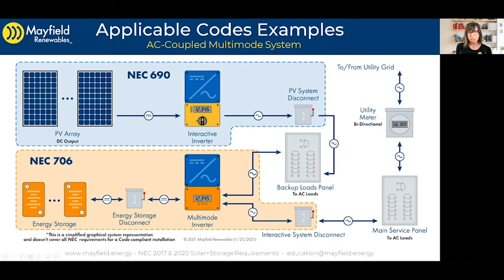The last thing to bring up is the voltage limitation. We need to keep in mind that DC circuits can't be over 600 volts DC on the DC side for a dwelling unit, unless they are not accessible during routine maintenance. We want to make sure we're considering that code requirement about DC voltage in our designs.